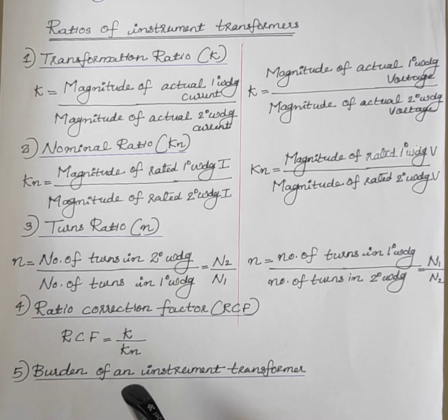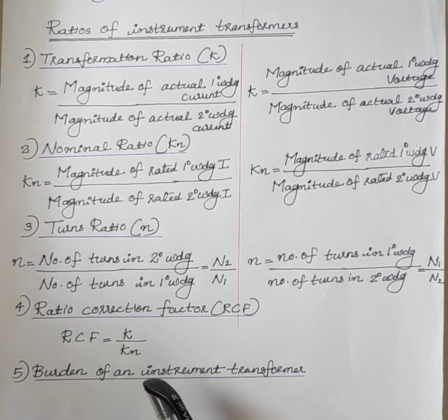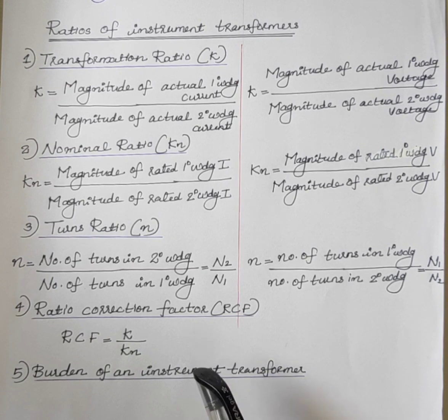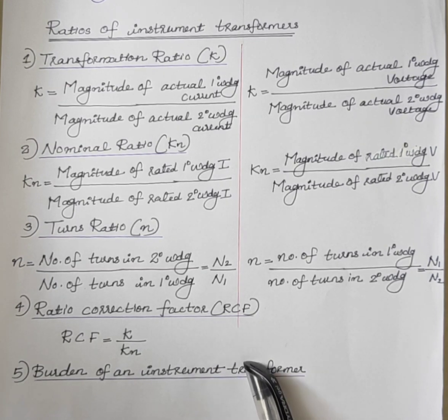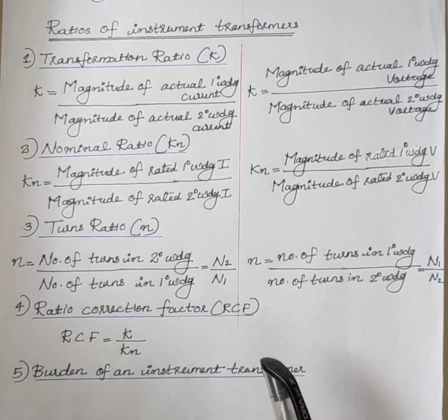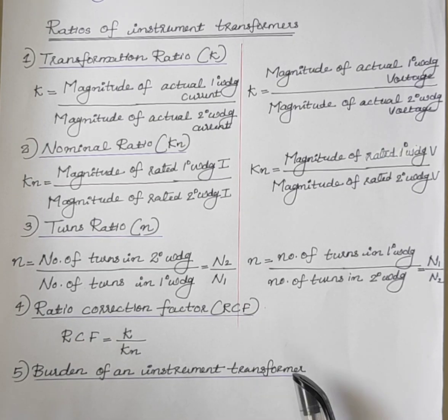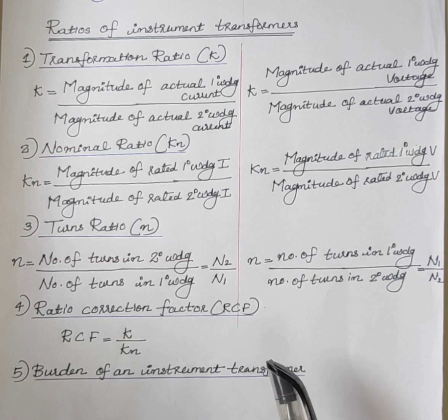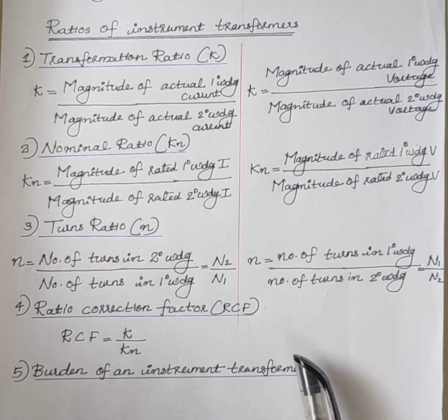Burden means the load across the secondary winding terminals. Burden is specified as volt ampere. The rated burden of an instrument transformer is defined as the maximum loading in volt ampere which may be applied across the secondary terminals such that errors do not exceed the limits.